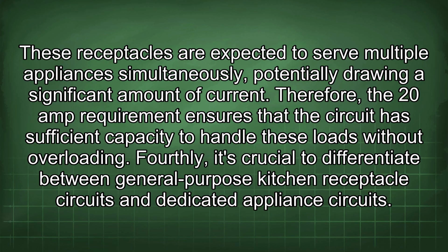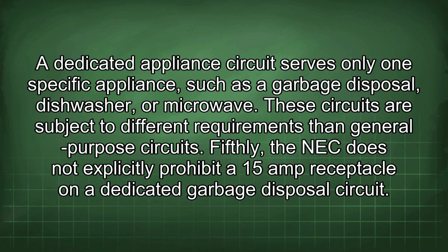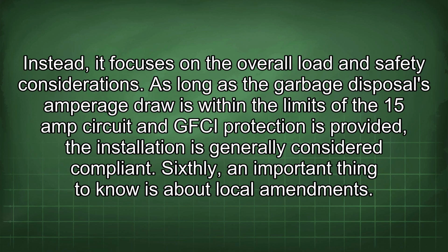Fourthly, it's crucial to differentiate between general-purpose kitchen receptacle circuits and dedicated appliance circuits. A dedicated appliance circuit serves only one specific appliance, such as a garbage disposal, dishwasher, or microwave. These circuits are subject to different requirements than general-purpose circuits. Fifthly, the NEC does not explicitly prohibit a 15-amp receptacle on a dedicated garbage disposal circuit. Instead, it focuses on the overall load and safety considerations. As long as the garbage disposal's amperage draw is within the limits of the 15-amp circuit and GFCI protection is provided, the installation is generally considered compliant.